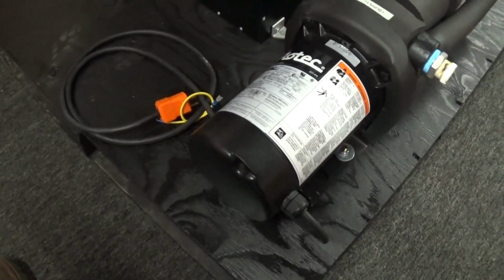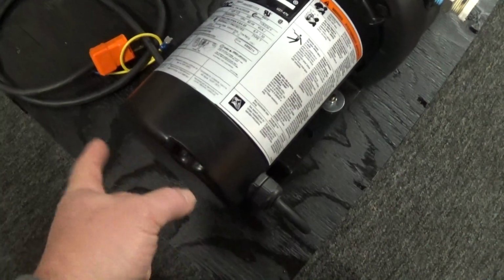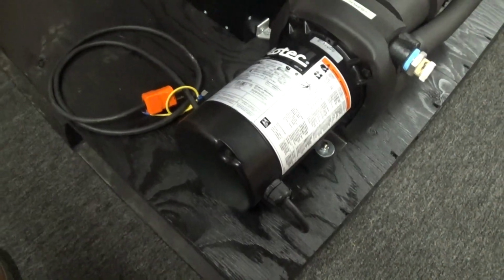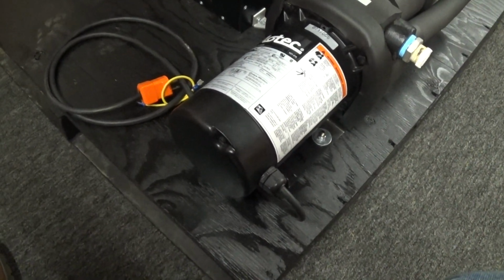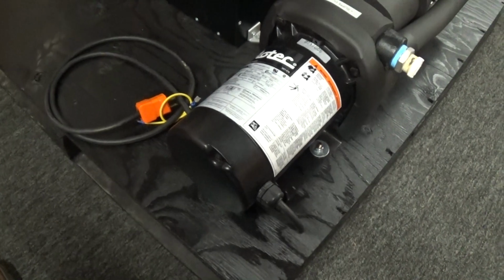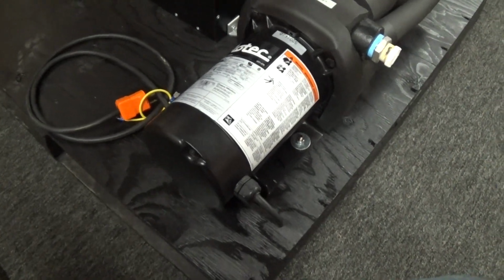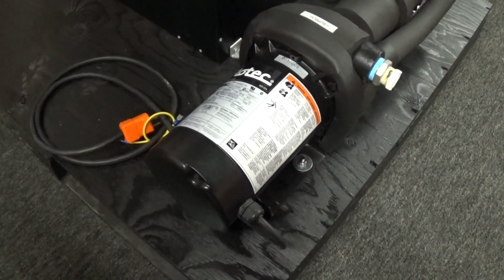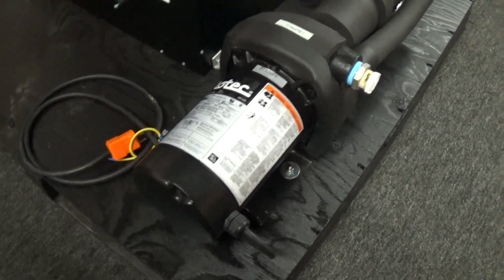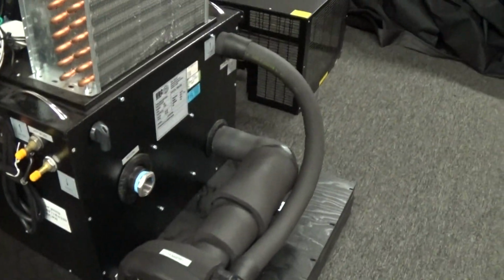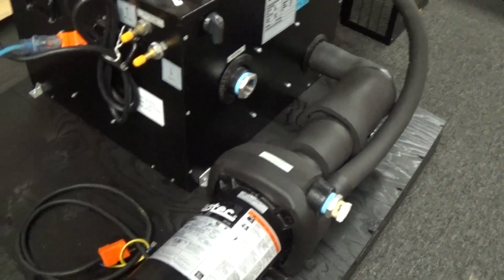Save that, because once your system's up and going, we're going to tell you how to check the amp draw. You simply take the end cover off the Glycol pump here and have a little simple amp meter. And once your system is up and running, we want to check that to make sure that you're not over amping on the Glycol loop.